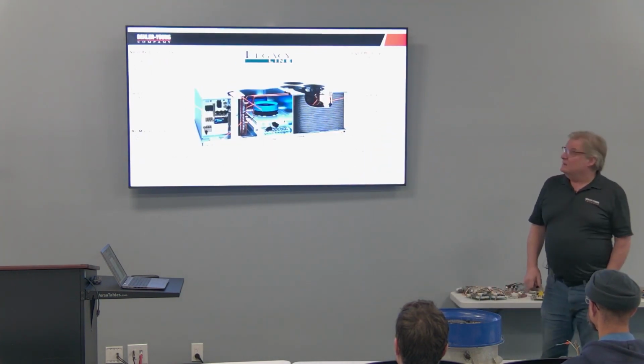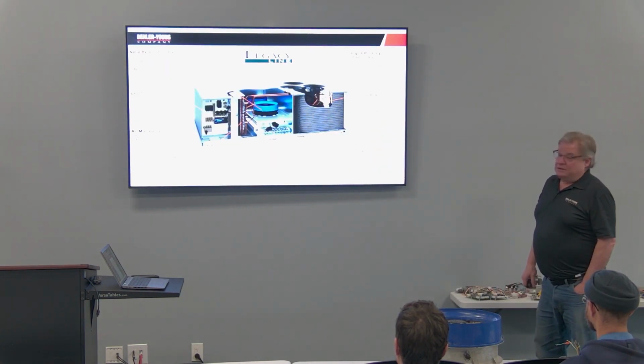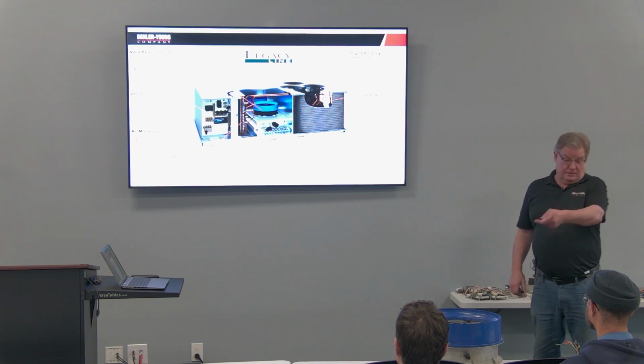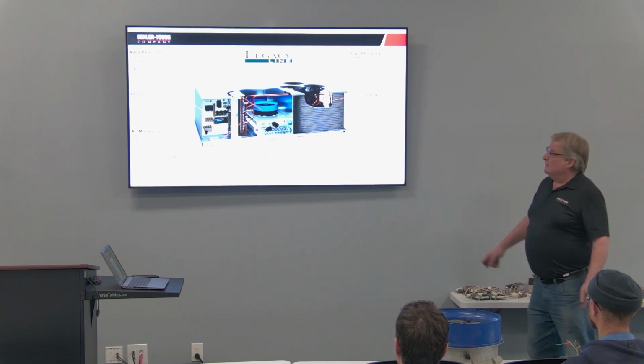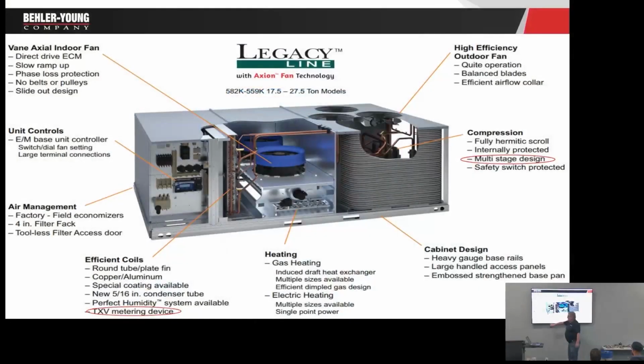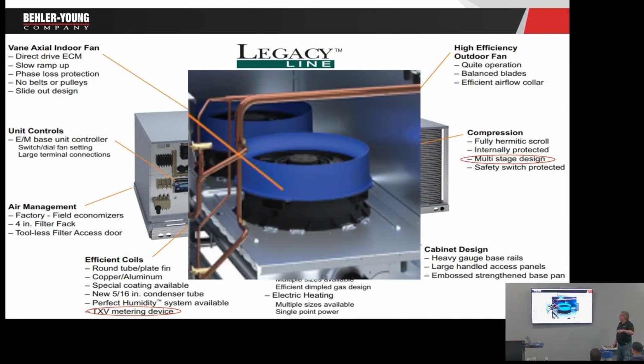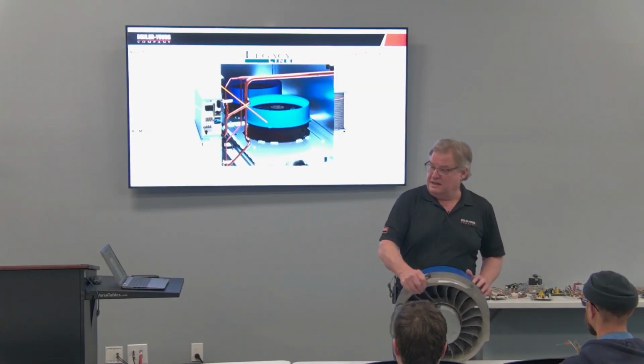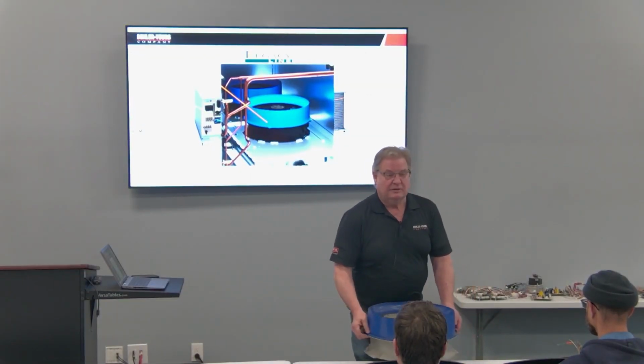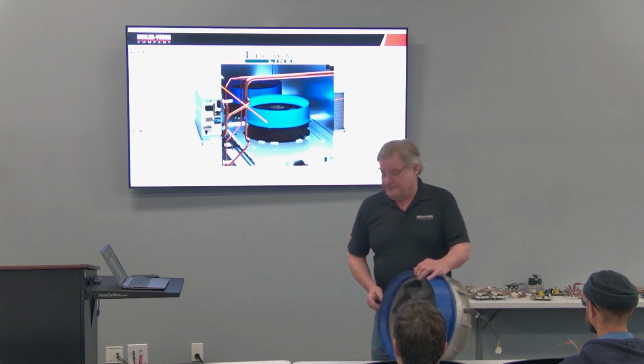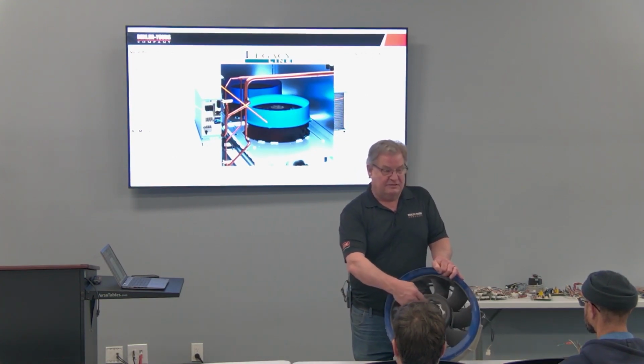And then we get into the big 17.5 to 27.5 ton unit. And we've gone to 2 of these. Okay. We've also gone, like I said, to the TXV. So we've got a TXV across the board now. And we went to the 2 blower motors. The blower motors are in a tray. So you slide the whole thing out. Okay. If you've never taken one of these out, you can see the 2 screw holes here. So this slides in this way. You remove 2 screws, it slides out. Okay. 5/16 nut driver. You take 8 screws out here.